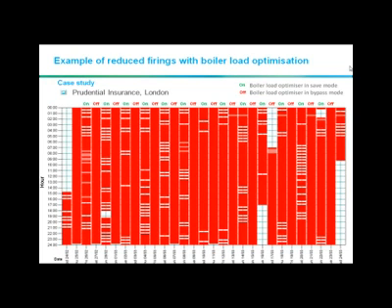Just as an example, here we have a slide that's giving a 24-hour operation across a month. The ladder effect that you can see here is where a system has actually been put into what's called a toggle mode. In other words, it's in a trial mode and it's actually doing what it's supposed to do on the tin on one day and not the next day.